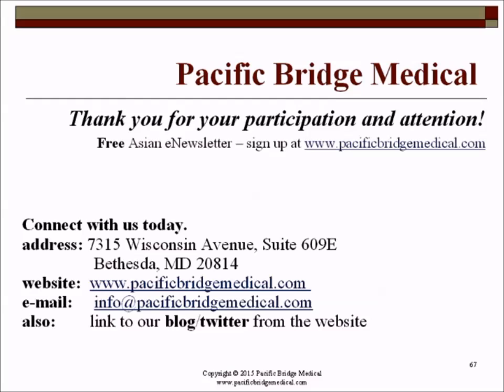But let me start with the questions because there's already quite a few. The first question here is, how long does a Class 1 notification take? Well, I'd say normally it takes about 1 to 2 months to prepare the dossier for the Class 1 notification in China. But once the dossier is assembled and all the documents are in place, the dossier can get notification or approval from the CFDA within 1 day. But the CFDA can also come back on your dossier for Class 1 notification and ask for some other documents or changes, which could delay the Class 1 notification to 2, 3, or 4 weeks. So normally, if everything's in order, it's supposed to be done the same day when you hand the documents in, as I mentioned in the webcast.